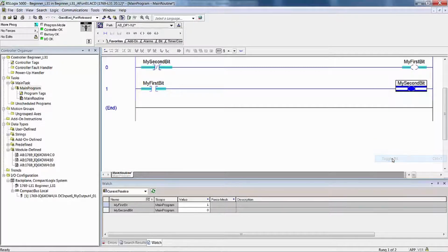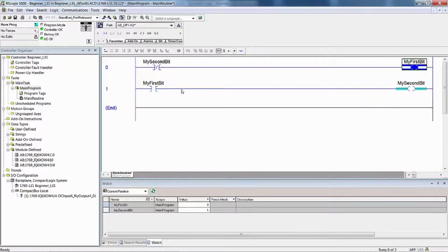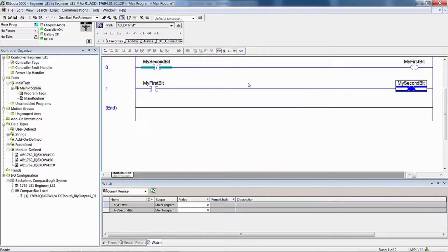And notice when I turn it on, this becomes false. So on the next program scan, this is false. So the false execution is to turn that off. If this is off, then this rung is false, and the false execution is to turn that off. But then you see in the next scan, this is now true. This was just for fun, scan-dependent logic.